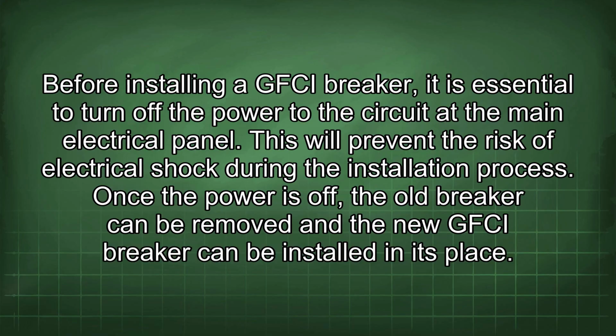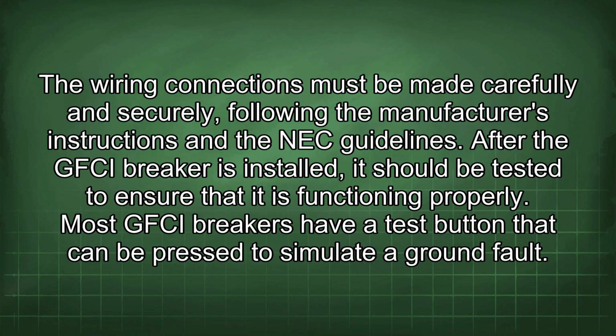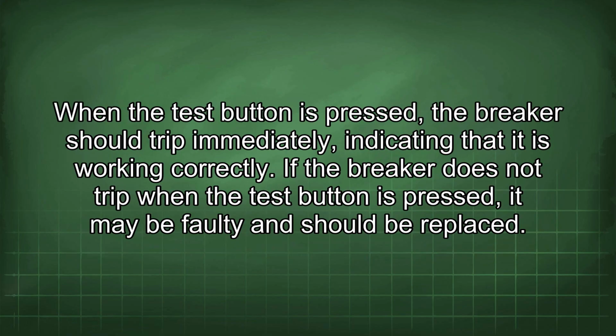Once the power is off, the old breaker can be removed and the new GFCI breaker can be installed in its place. The wiring connections must be made carefully and securely, following the manufacturer's instructions and the NEC guidelines. After the GFCI breaker is installed, it should be tested to ensure that it is functioning properly. Most GFCI breakers have a test button that can be pressed to simulate a ground fault. When the test button is pressed, the breaker should trip immediately, indicating that it is working correctly. If the breaker does not trip when the test button is pressed, it may be faulty and should be replaced.